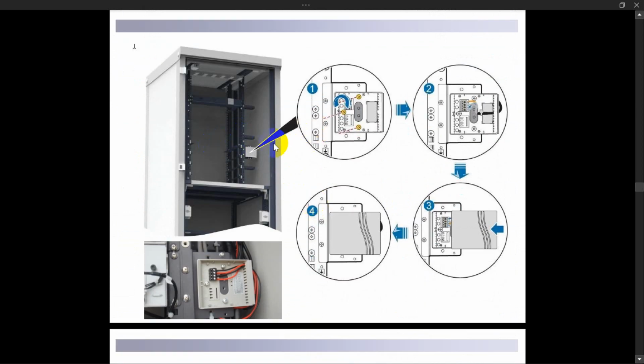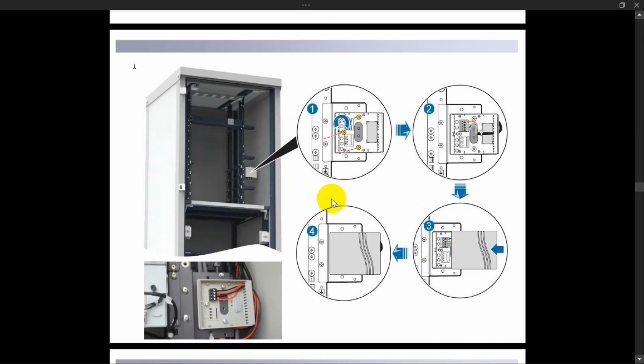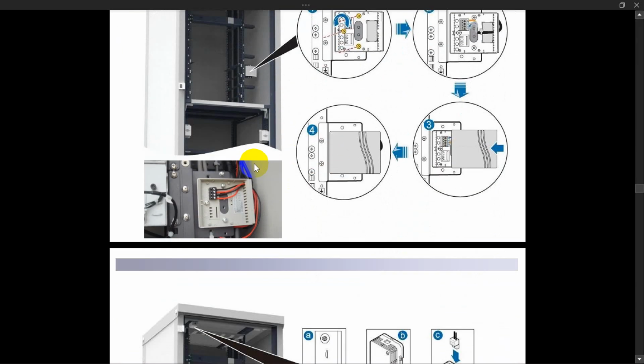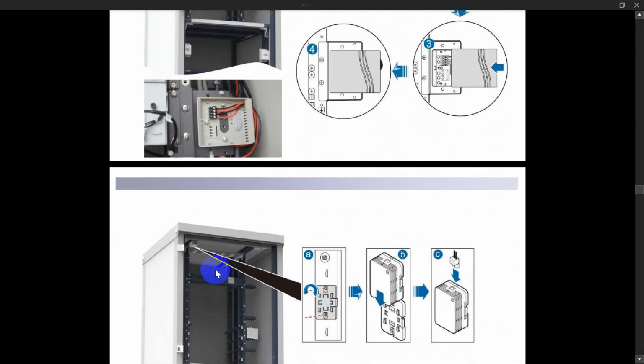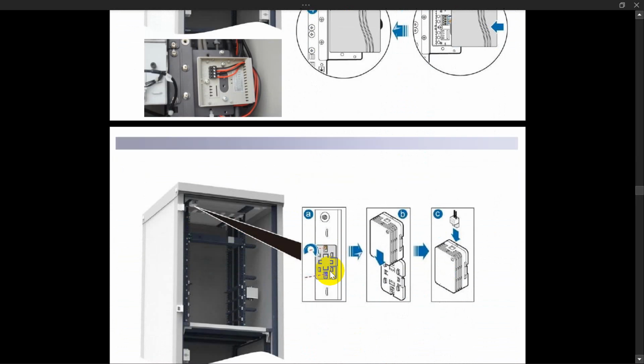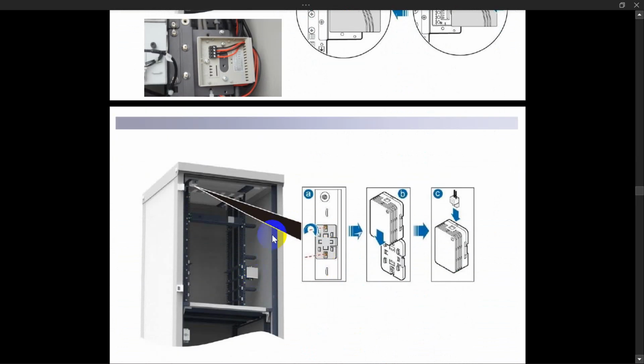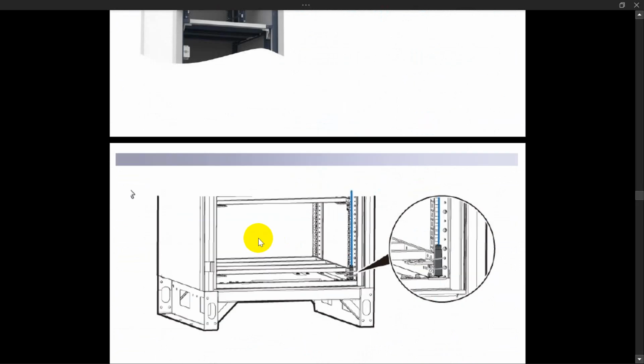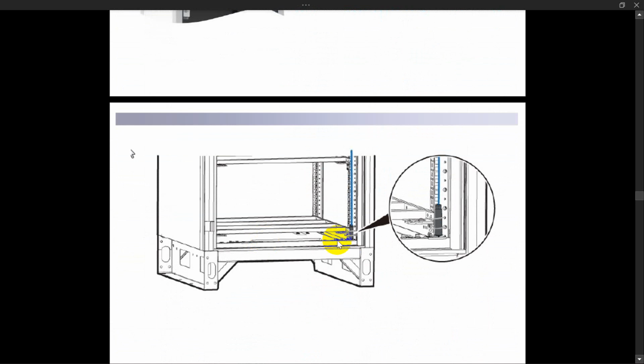Each type of sensor we are fixing inside the chassis of the 19-inch rack. If it is smoke or door, the door sensor will be beside the door from the upside, so once the door is open, it will give a door alarm. The smoke sensor can be on the side with the temperature sensor. The water sensor we usually fix down at the bottom of the rack, so it will get the water alarm if any water comes up to this level.